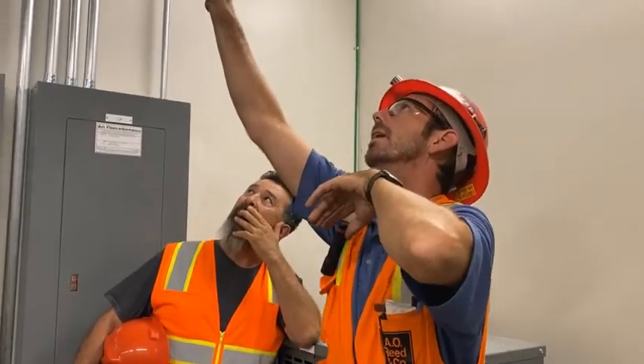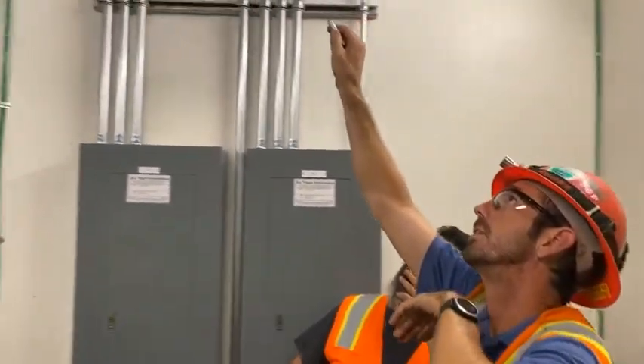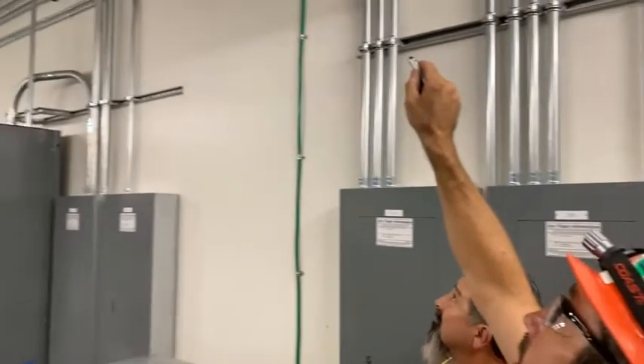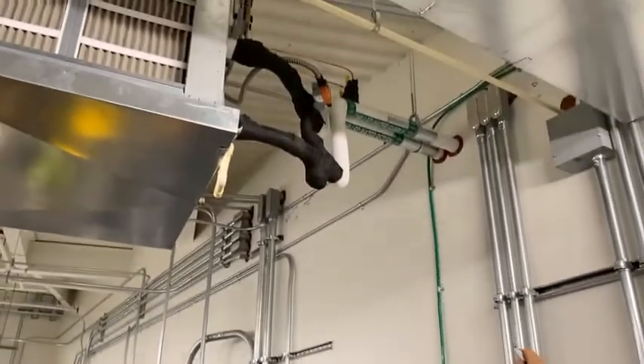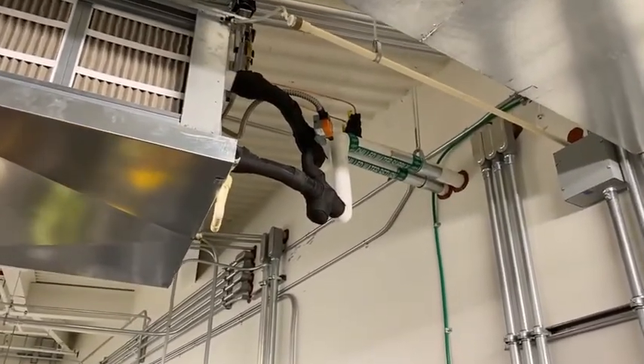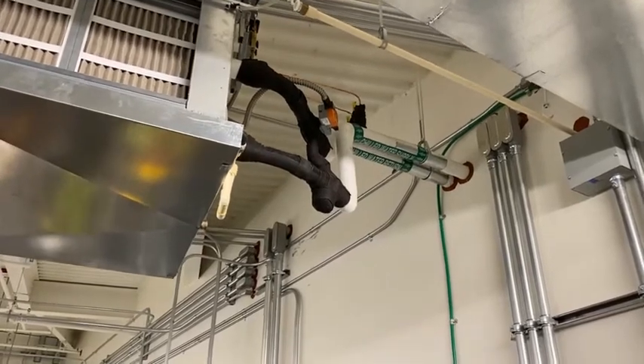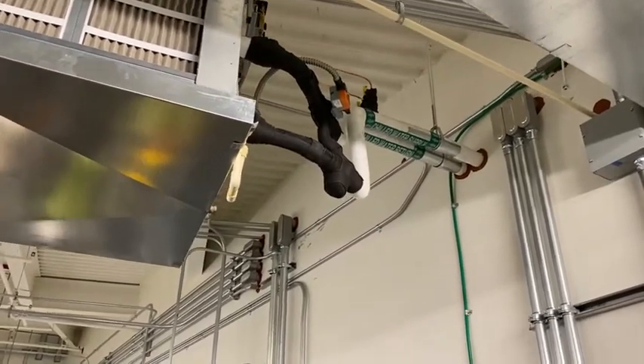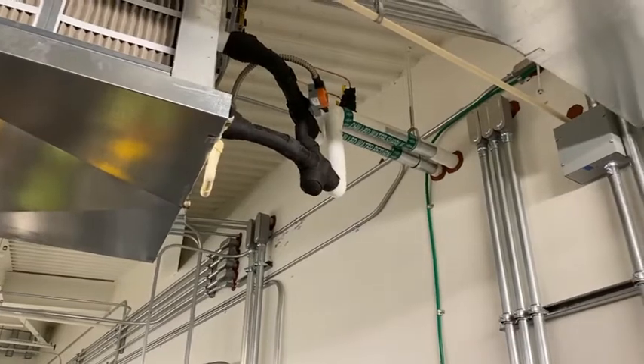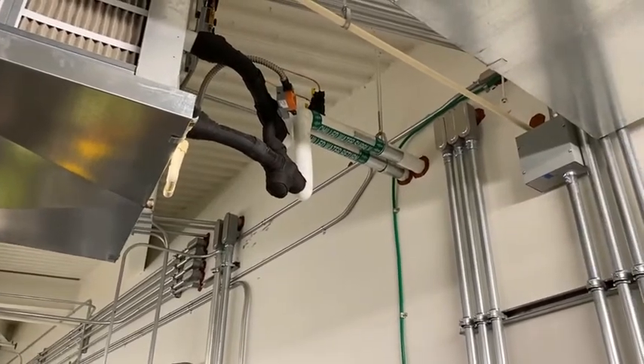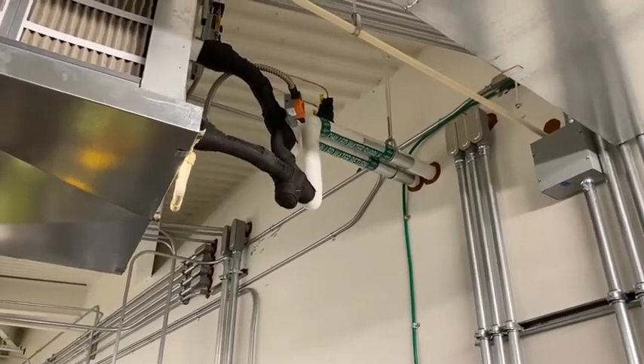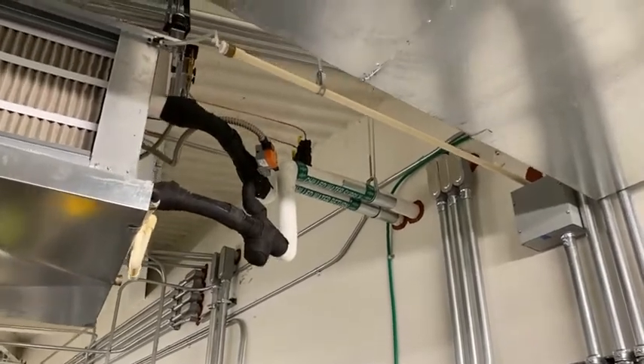The copper pipes right here, this is going to be your DP control for the chilled water pumps for building B. This differential pressure is what's speeding up and slowing down the pumps, we did training on that the other day. Since this valve is 100% open, the bypass is closed, and all the water is going through the coil. If it was halfway, you'd get half and half.